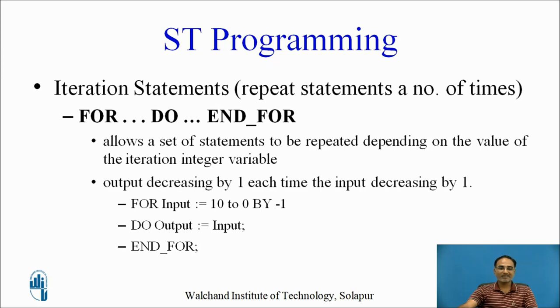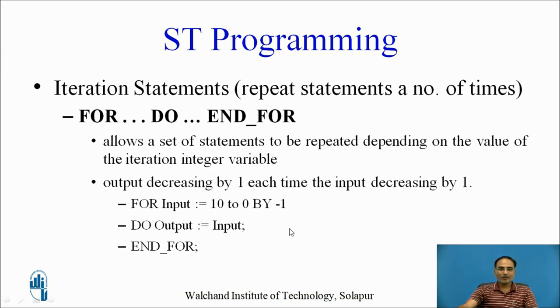Next are the iteration statements, which repeat for a number of times. The first iteration statement is FOR-DO, which allows a set of statements to be repeated depending on the value of an iteration integer. For example: FOR Input := 10 TO 0 BY -1 DO Output := Input END_FOR. This loop gives an output decremented by 1 each time the input decrements by 1.